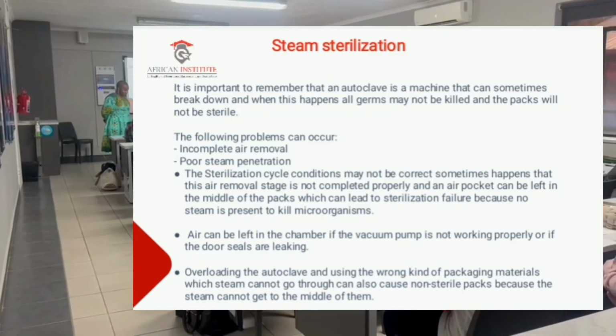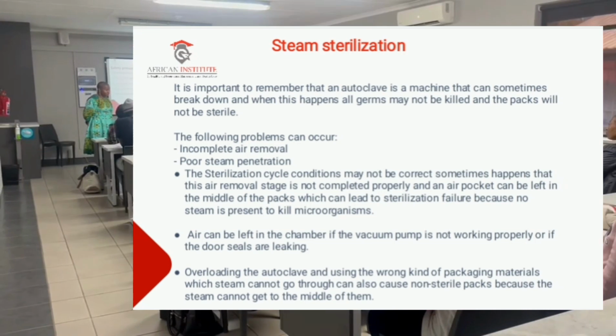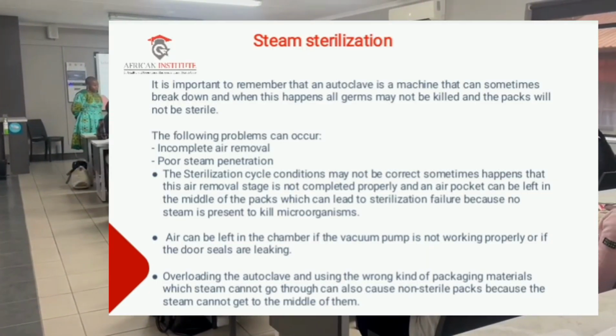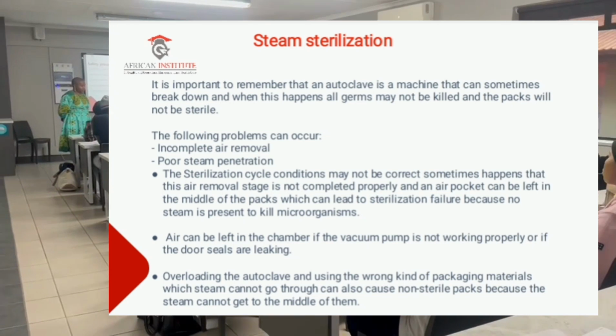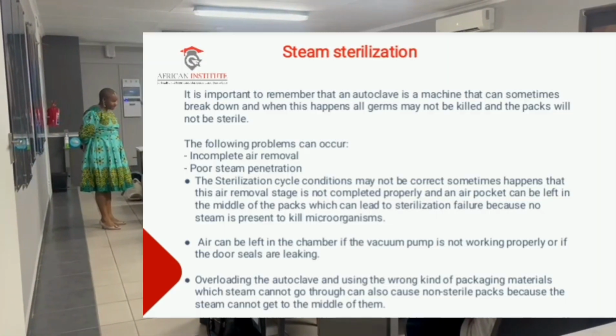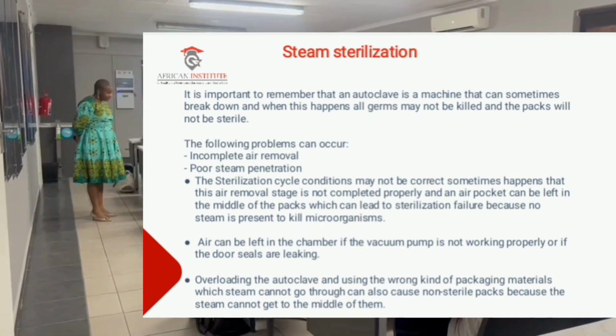It is important to remember that an autoclave is a machine that can sometimes break down, and when this happens, all germs may not be killed and the packs will not be sterile. The following problems can occur: incomplete air removal, poor steam penetration, and the sterilization cycle conditions may not be correct. If the air removal stage is not completed properly, an air pocket can be left in the middle of the pack, which can lead to sterilization failure because no steam is present to kill microorganisms, and your chemical indicator might not change properly.